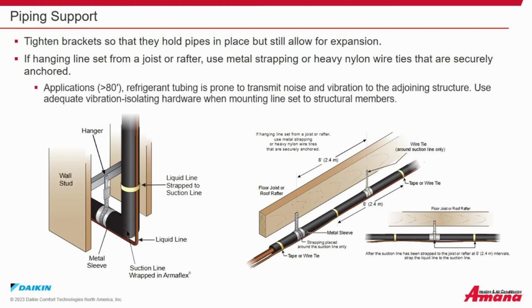Applications longer than 80 feet. Refrigerant tubing is prone to transmit noise and vibration to adjoining surfaces. Use adequate vibration isolating hardware when mounting line sets to structural members.